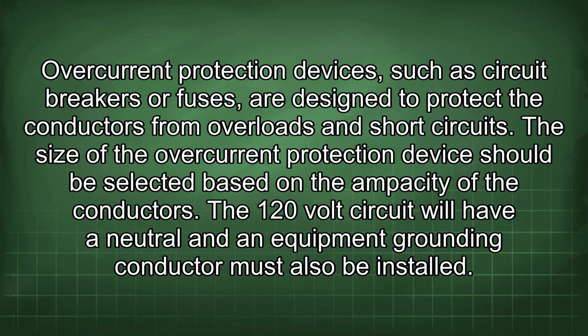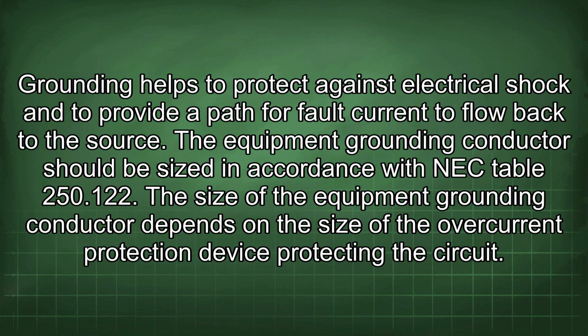The 120-volt circuit will have a neutral, and an equipment grounding conductor must also be installed. Grounding helps to protect against electrical shock and to provide a path for fault current to flow back to the source. The equipment grounding conductor should be sized in accordance with NEC Table 250.122. The size of the equipment grounding conductor depends on the size of the overcurrent protection device protecting the circuit.